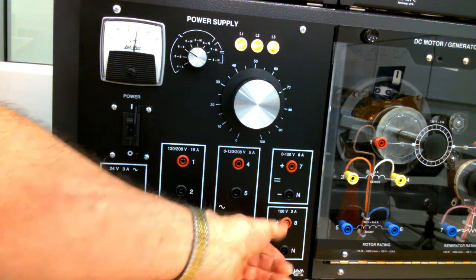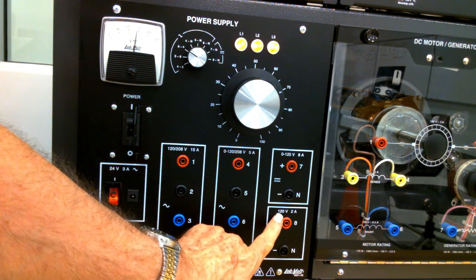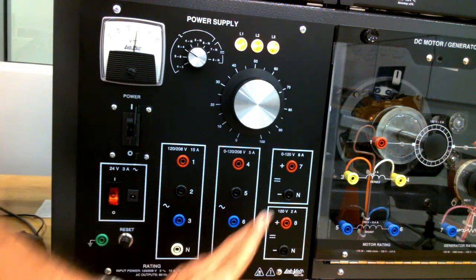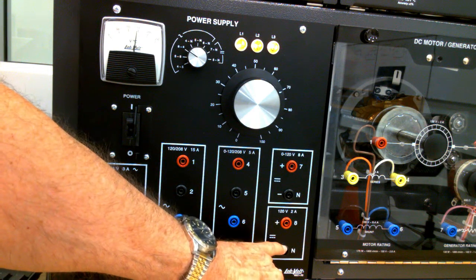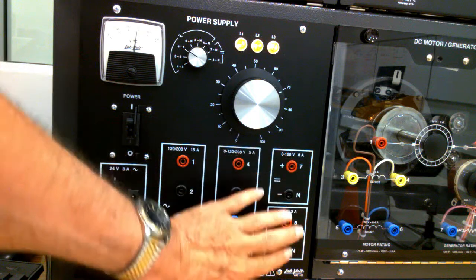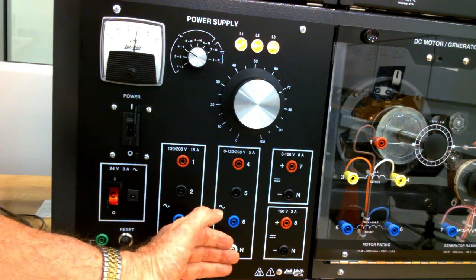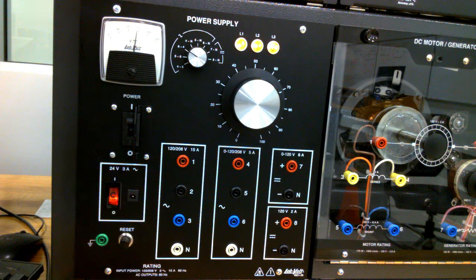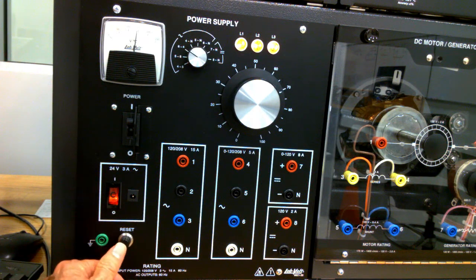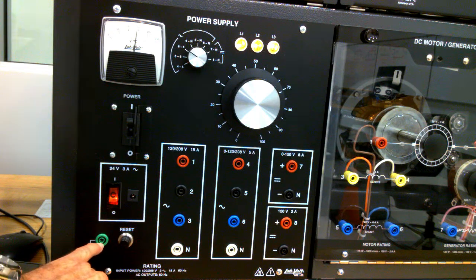This one is fixed, okay? It is only 120 volts. You can't vary it with respect to neutral. This one's variable, this one's fixed. These are variable, these are fixed. There is circuit breaker protection on this module. Here's the reset button in case you trip it, and we're very happy to have a circuit breaker on this rack. Okay, and this right here, green, as always in the electrical system, is earth ground.